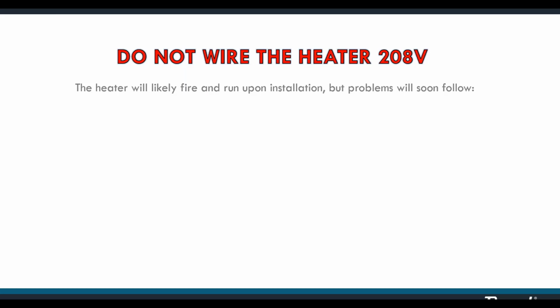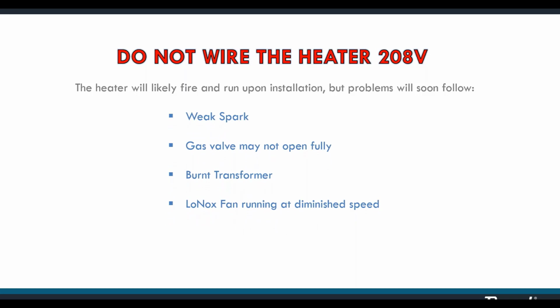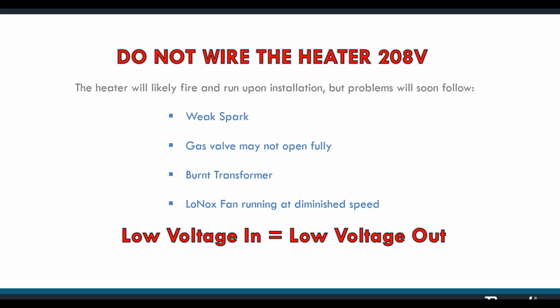Check the voltage at the installation point to verify that it's in range. Occasionally, you may find the voltage on your 240 line to actually be 208. This most likely means you have 3-phase electrical, often found at commercial buildings. Do not wire the heater for 240 operation if the incoming voltage is 208. All right. Remember, low voltage in means low voltage out.